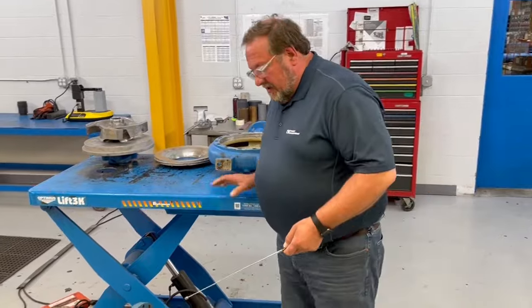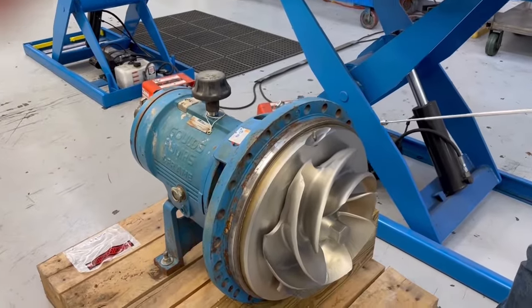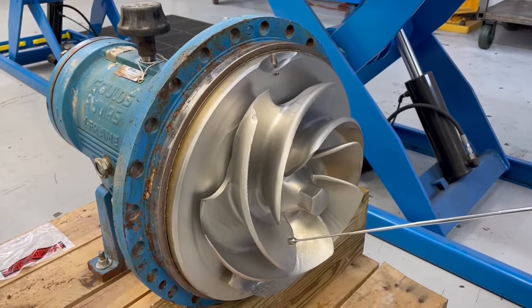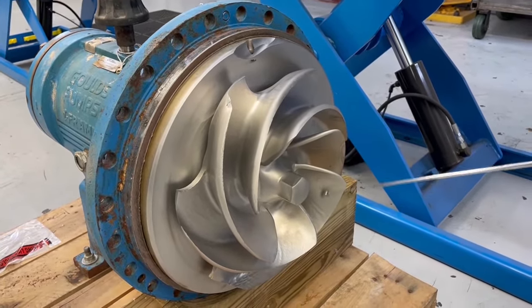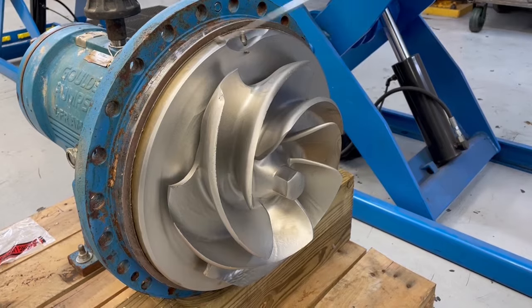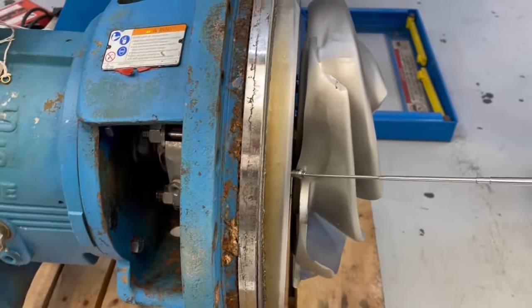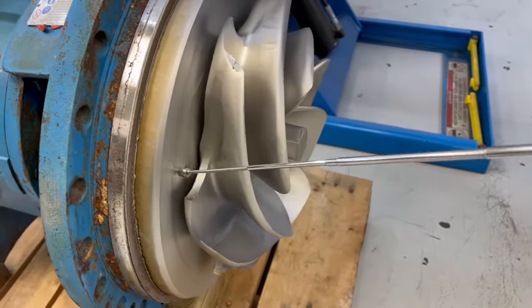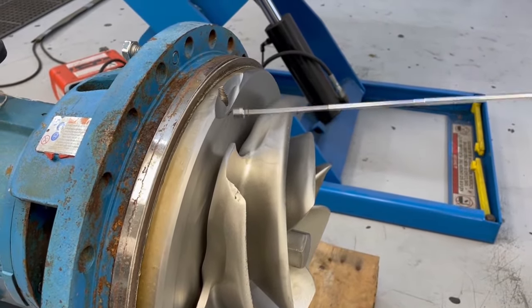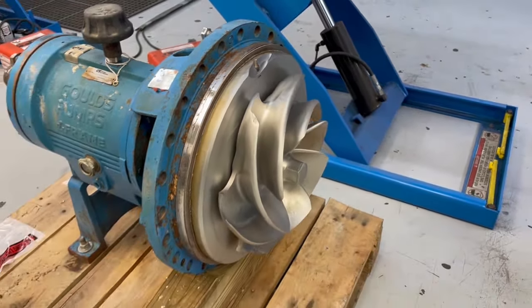This next example is a Goulds 3196 XLT pump. This particular back pull-out assembly has significant abrasive wear throughout. You can see not only wear and irregularities on the working area of the impellers, but on the face that goes against the casing as well. The back pump-out vanes are nearly gone on the backside, and you can see cupping on the stuffing box cover going across from the center outward. Up near the cutwater area in the casing, there's also an extreme amount of washout. This is clearly an abrasive wear example.